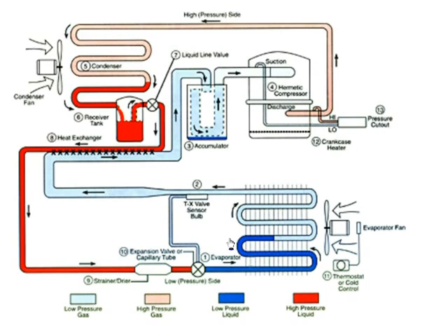Alright, and this is your door to your coil box here. If you just take your temperature right here, you strap on your little thermometer and take your temperature right here, and you just subtract the two, that's your superheat. You don't need to go to your outside unit and hook up gauges to see what superheat is. That pressure right there, if everything's working right, is going to be the same as the pressure right here at the unit. You don't need to hook up your gauges.